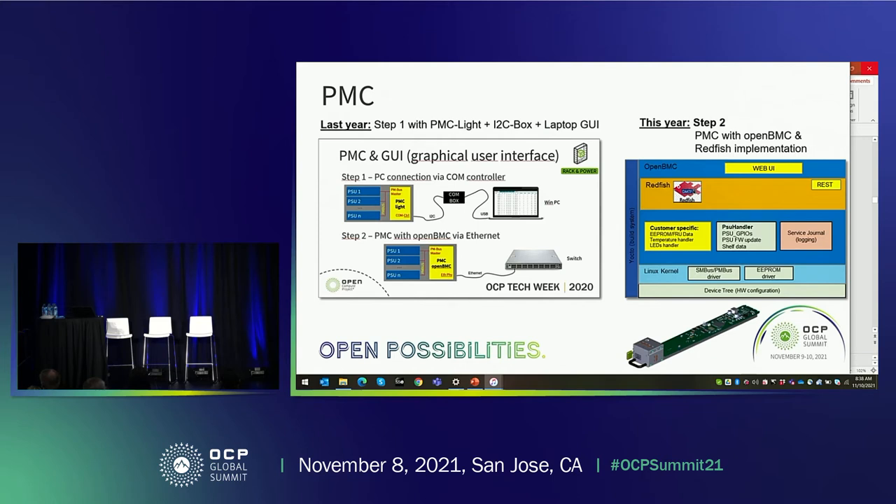In the middle on the right side is the block diagram. Starting from the bottom is the device tree — the hardware configuration — then the Linux kernel with SMBus and PMBus drivers as well as the EEPROM driver to communicate with the EEPROM inside the shelf. Above that we have customer-specific data: EEPROM and FRU ID, a temperature handler, LED handler, and PSU handler to talk to the power supplies and fetch data, plus a service journal for logging. All of this runs under Redfish and the REST API, with a web UI where you can log in to the shelf and monitor all power supplies.